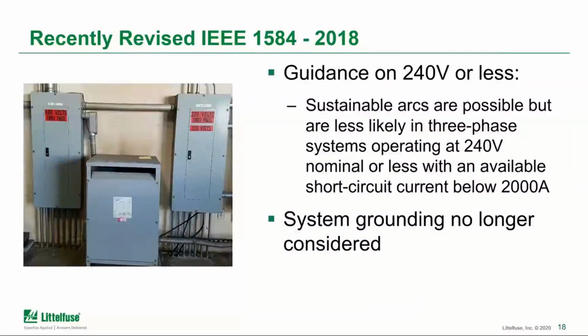Another point of interest: in the previous standard, there was an exemption for less than 240 volts, less than 125 kVA. That exemption has been removed and replaced with a statement that I've put in here verbatim: sustainable arcs are possible, but are less likely in three-phase systems operating at 240 volts nominal or less with an available short circuit current below 2000 amps. And another bullet point there: system grounding is no longer considered as part of that. So there's no longer a penalty applied for an ungrounded system in that calculation.